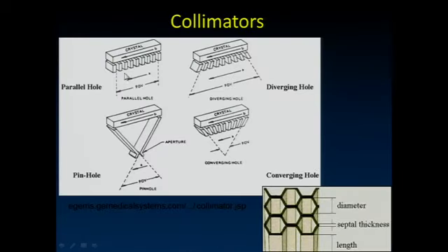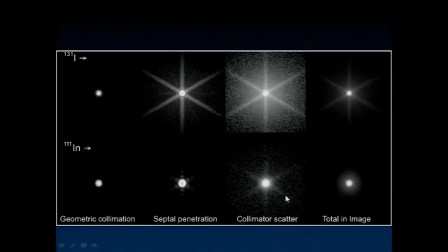We talked about the fact that the collimator is made out of lead, and oftentimes it's made out of these almost corrugated pieces of lead that, when they're stacked together, form these hexagonal holes, if you will. Of course, the higher energy some of these radionuclides are, here's I-131, which is a beta emitter, but also decays through the production of some high-energy gamma rays, they will frankly pass right through the thin lead septa of some collimators.